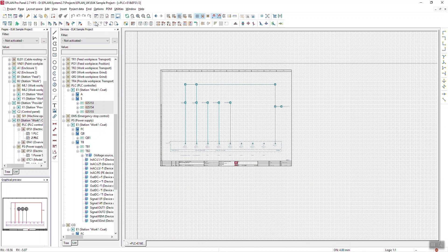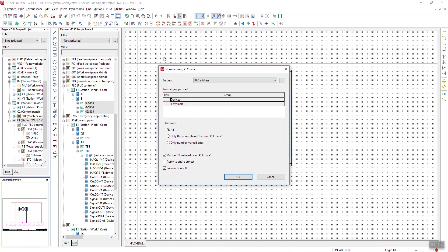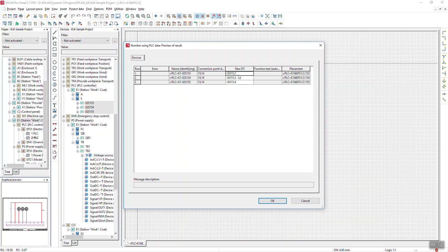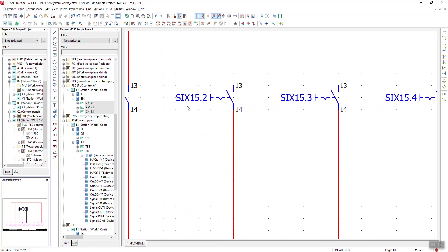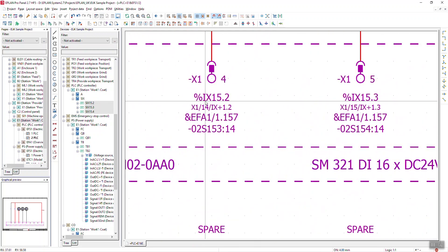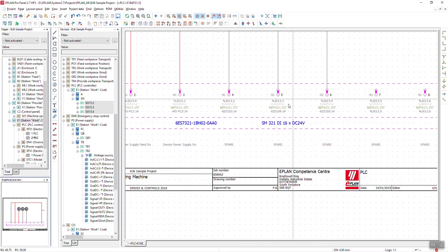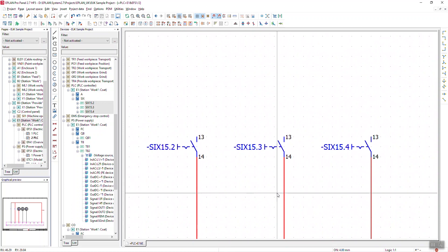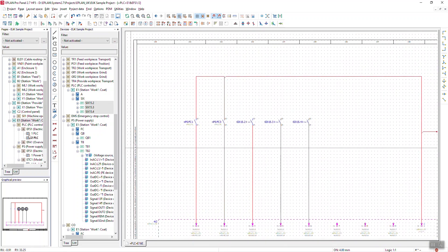I mentioned you can also do things via PLC. I select the section I want, go to Project Data > Devices > Number Using PLC Data, click onto my device set, and click OK. I can now see I can change my switches to have details from my PLC. In here it shows S for switch, IX 15.2, and that matches up with IX 15.2, 15.3, and 15.4 from the PLC data. Not only will it do inputs, it will also do outputs too.